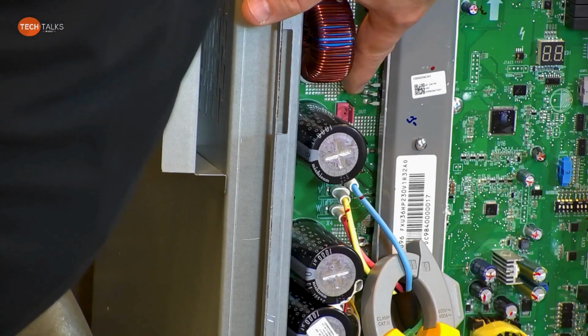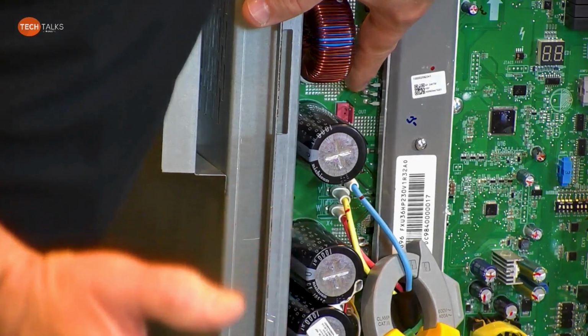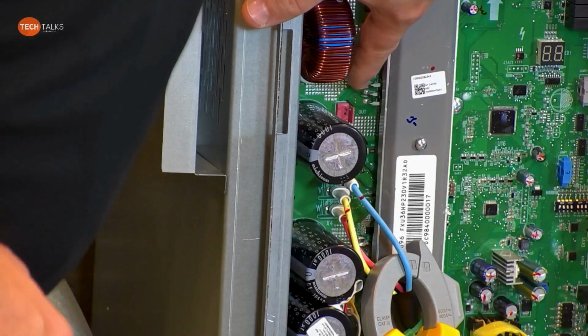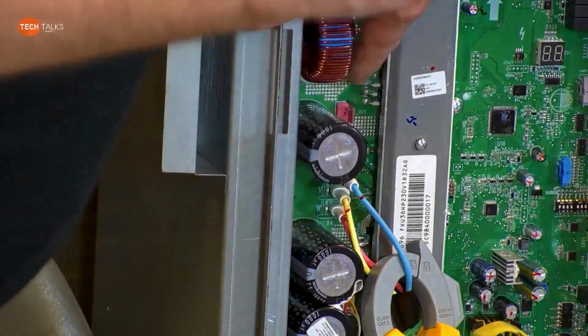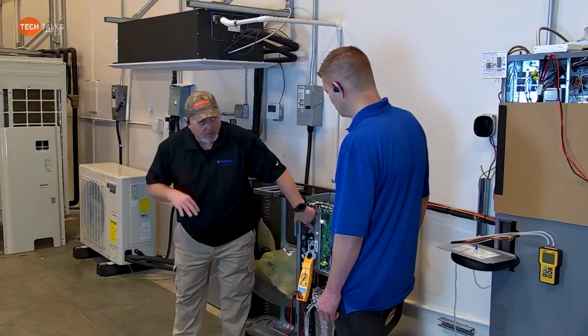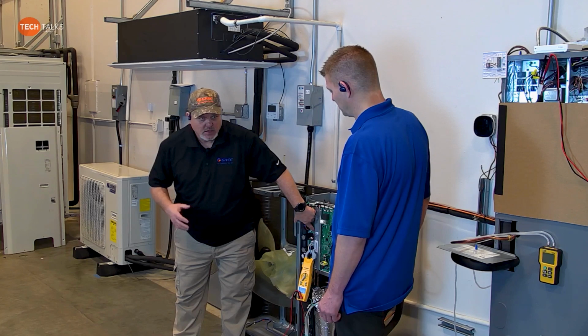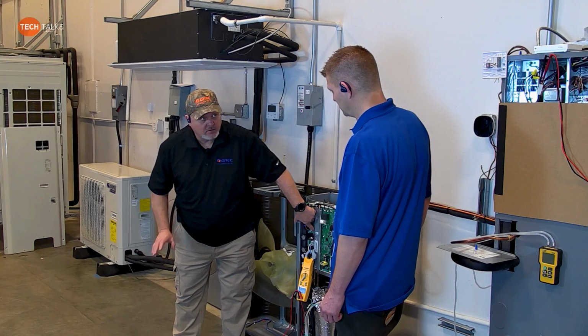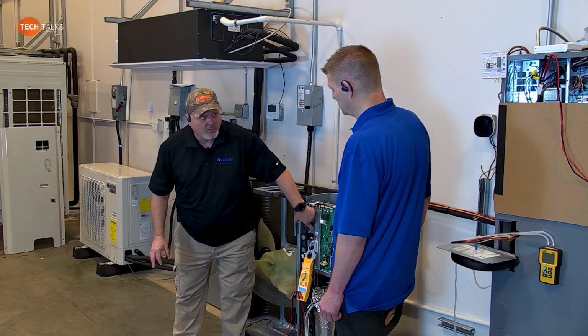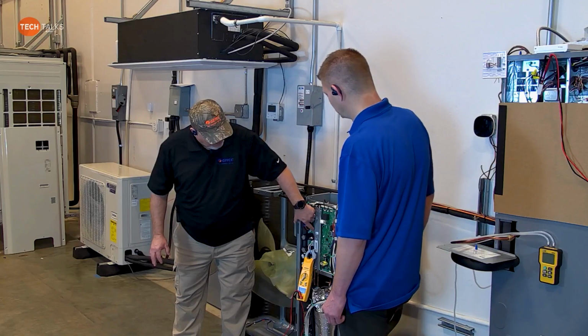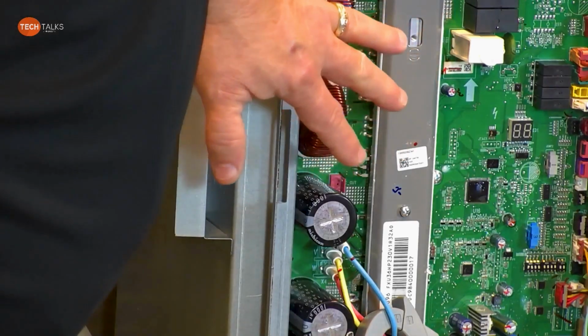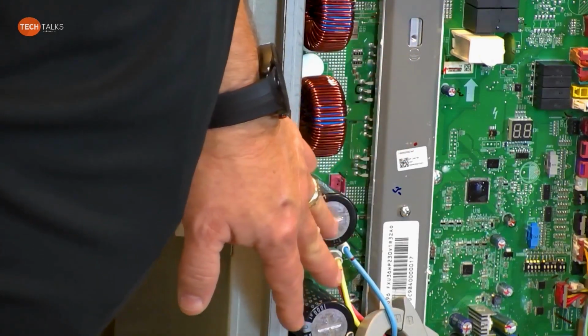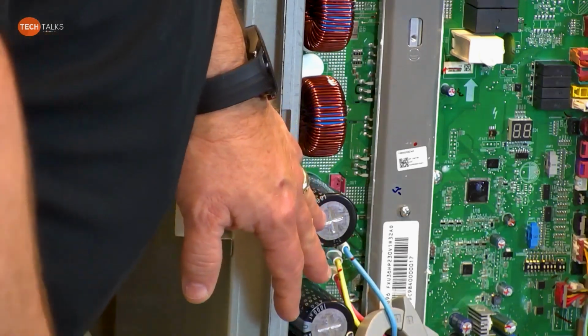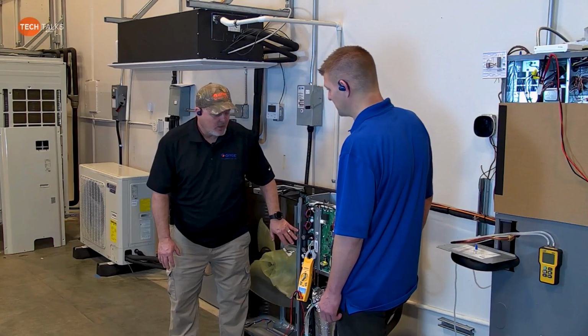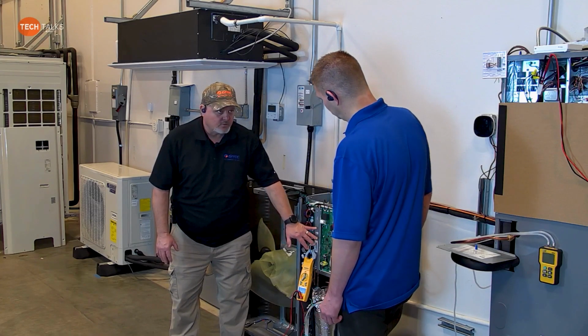So guys, I'll tell you, for safety reasons, for multiple things that we talk about here, you can watch that light, and we did it yesterday. We powered it off and watched the DC bus. That light never went all the way out until we were well below about 3 volts DC. Yep. But my concern with everybody here is these capacitors: you touch that capacitor and you're standing on wet grass, you're going to get it. So it's all about safety as far as I'm concerned.